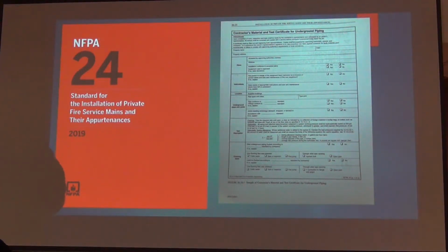Okay, this was a 4-story building with a dry suppression in the attic space, and a dry suppression for the parking underneath. I was downstairs in the sprinkler riser room when they activated the inspector's test, which is at the far end of the dry system, and all I heard was bang, bang, bang, bang, bang. Like, what the? And I didn't even get a chance to get the rest of those words out when the building inspector, electrical inspector, and general contractor were calling me saying, "Did you hear all that?" This went all the way through the system.